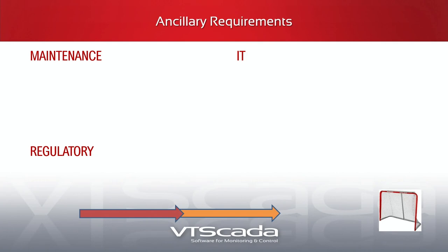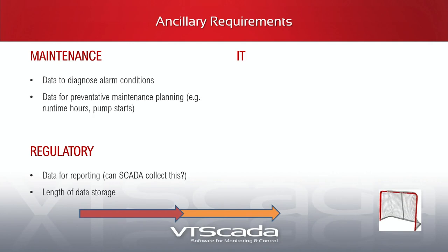There are additional requirement categories: maintenance data to diagnose alarm conditions — your trending information and ancillary data showing values that affect the process around the one you're looking at. You'd want the ability to trend values associated in groups. For preventive maintenance: runtime hours, pump starts. If we can use that information to generate low-priority warnings when something needs maintenance, that's helpful — and we already have that information in the system.